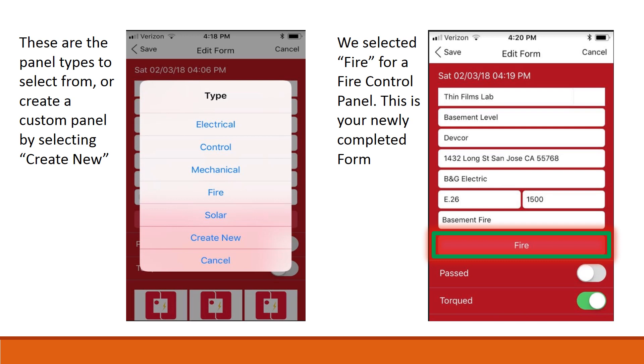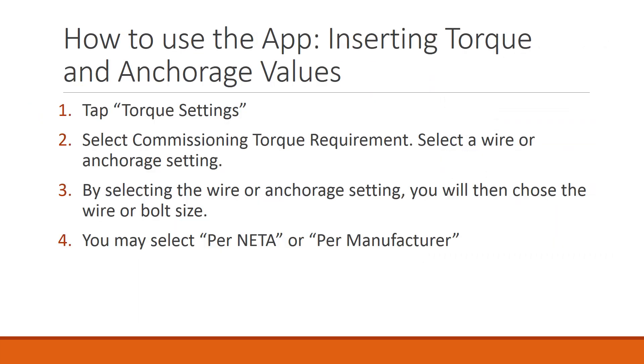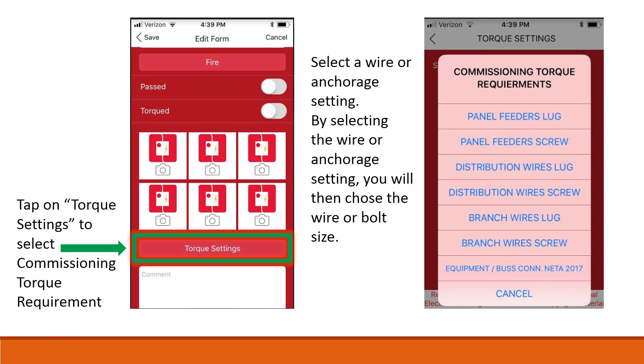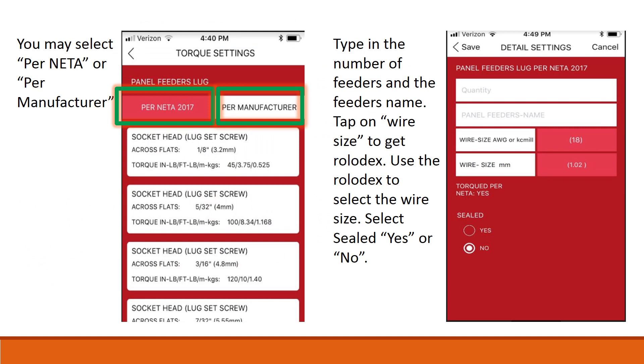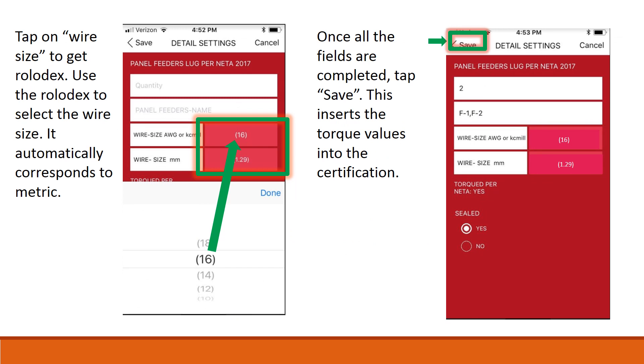Inserting torque and anchorage values. Tap Torque Settings. Select the commissioning torque requirement. Select a wire or anchorage setting. By selecting the wire or anchorage setting, you will then choose the wire or bolt size. You may select Per NETA or Per Manufacturer. Type in the number of feeders and the feeder's name. Tap on Wire Size to get the Rolodex. Use the Rolodex to select the wire size. Select seal Yes or No. It automatically corresponds to metric. Once all the fields are completed, tap Save. This inserts the torque values into the certification.